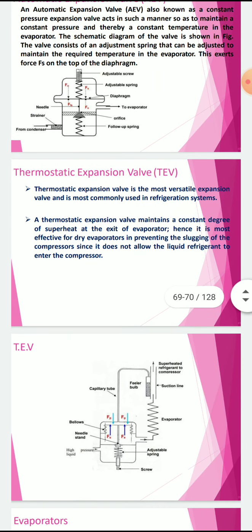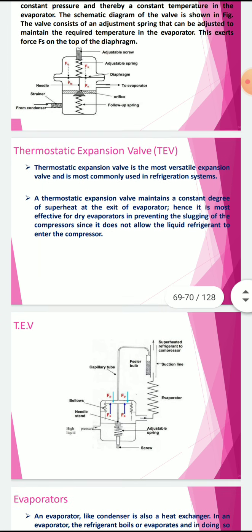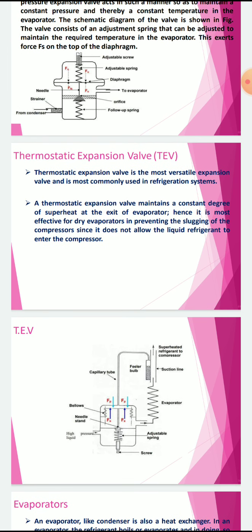Now, thermostatic expansion valve. The thermostatic expansion valve is the most versatile expansion valve and is most commonly used in refrigeration systems. Thermostatic expansion valve maintains a constant degree of superheat at the exit of evaporator.